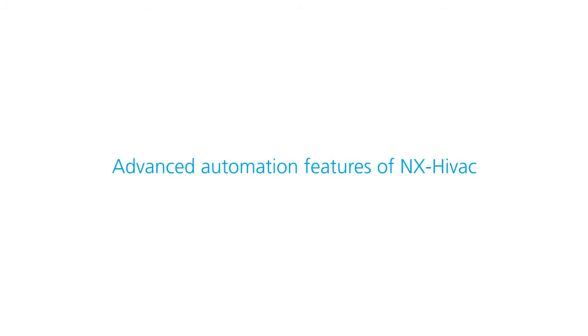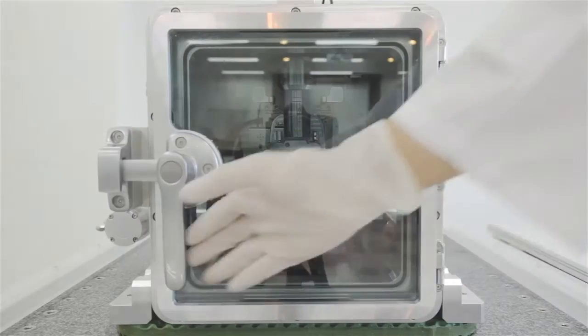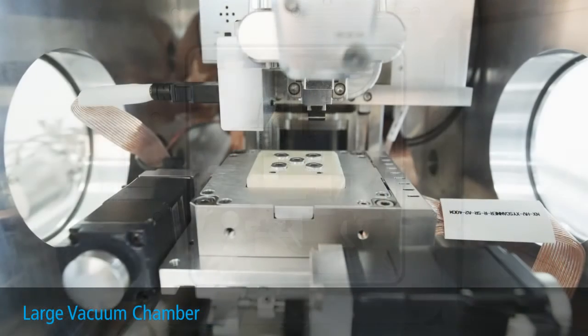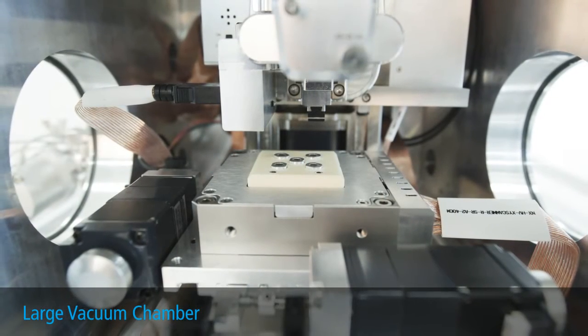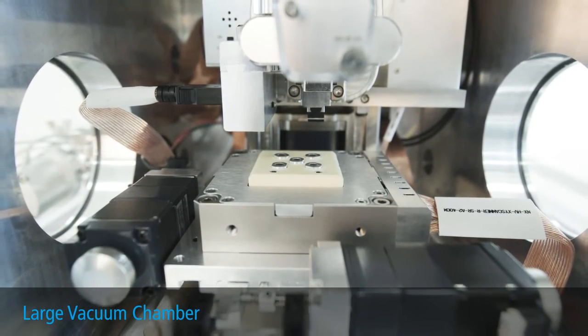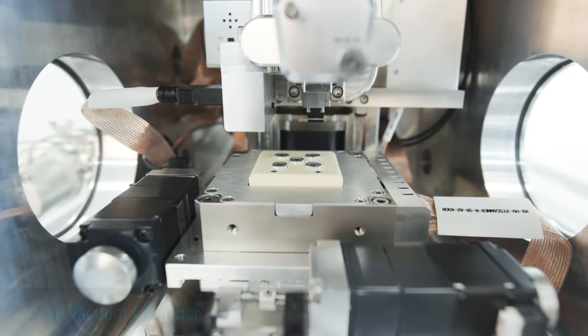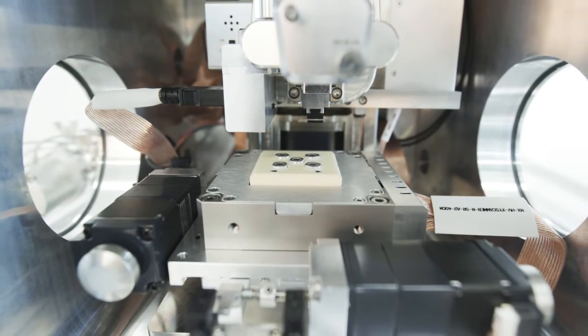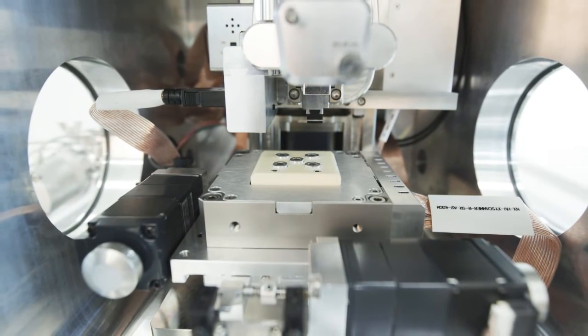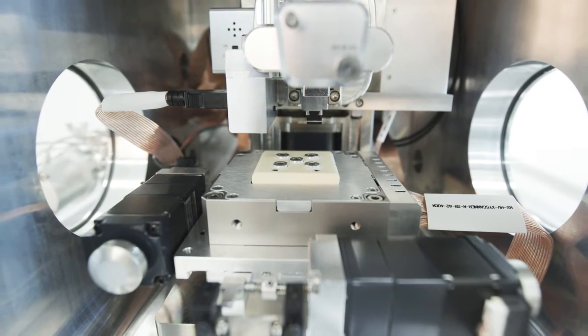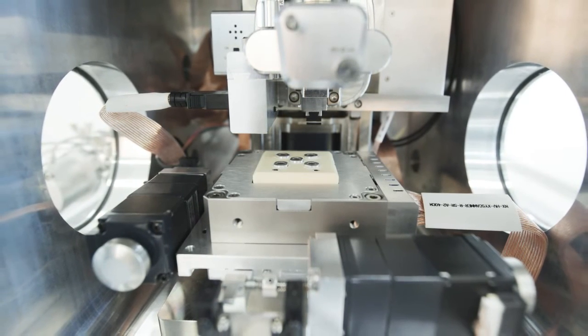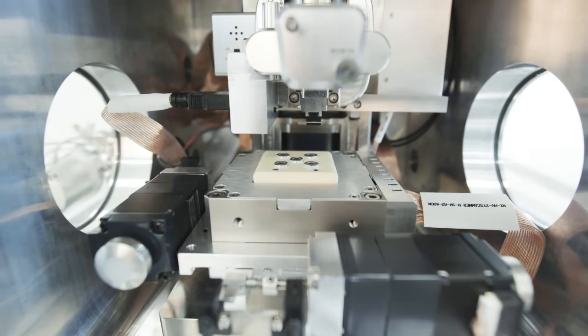Let's run through some key features of Park NX-Hivac. First, Park NX-Hivac has a large vacuum chamber, spacious enough to handle samples of various sizes. Like other Park AFM systems in our NX product line, the Park NX-Hivac has decoupled XY and Z scanners. This architecture removes scanner artifacts, enabling the most accurate AFM imaging possible.